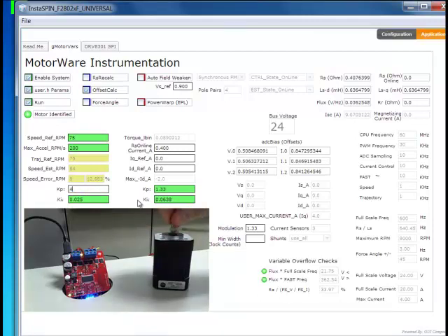And if you add any sort of load, remember that the performance here at lower speeds is based on the back EMF. So part of that is the flux value of the motor. And this is a motor with 0.035 volts per hertz. So at 5 hertz, we're getting 0.035 times 5, so a relatively small amount of flux.